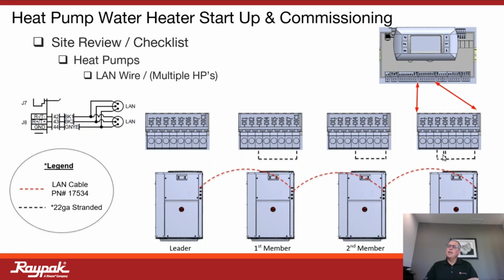So what this really does is, the leader is going to engage based on a set point demand, and then everything in sequence connected to it as a follower will follow suit. So these jumper wires essentially set the personality of the follower, so that this jumper that you see right here will recognize that, hey, I'm the first one attached to the leader. I'm the second one attached to the leader. I'm the third one attached to the leader, as it were. Very, very straightforward, as it pertains to wiring. And there is a programming that will follow suit here that we'll talk about as well.